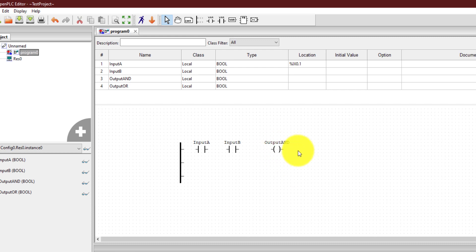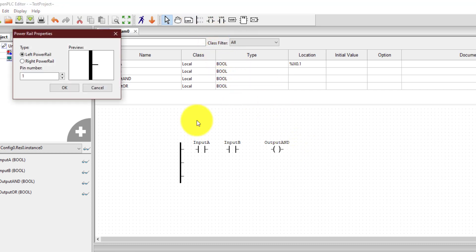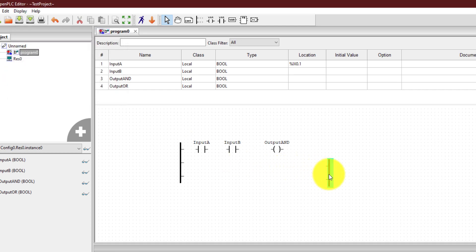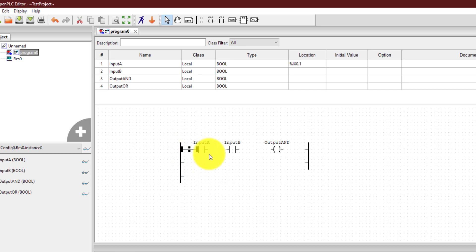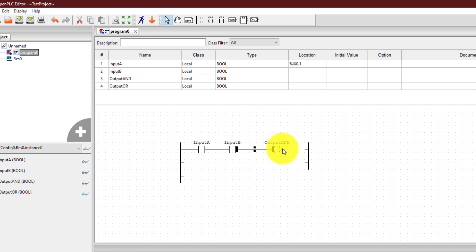I can place the output coil over here, and at the end I need a right side power rail. To create that, once again click the power rail icon, click somewhere, and this time click on right power rail. For the right power rail I need two pins — one for the AND rung and the other for the OR rung. So I'm going to add two pins. Now I just need to connect these elements. For connection, bring your mouse over and click and drag to connect the elements — joining input A with input B, and connecting the remaining elements as well. We have implemented the AND gate.